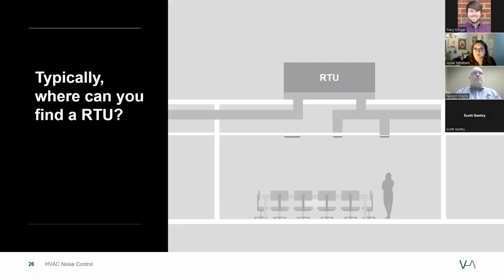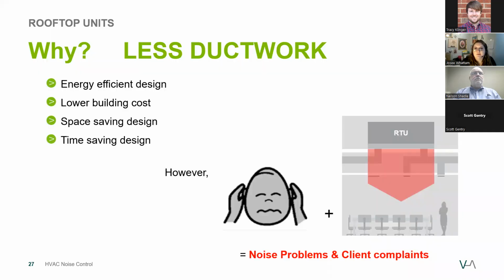However, typically, where can we find an RTU? That's right, over occupied spaces. There are multiple benefits to an RTU placement over an occupied space. Most of these result in less ductwork being required. Energy is conserved by design because there is less pressure drop and thermal losses, lower material and installation costs, ceiling space is saved by ducting directly into the space, and design time is reduced when less runs are required.